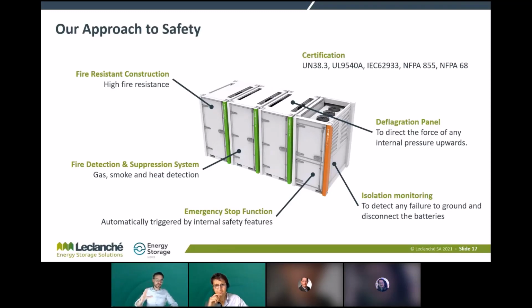The biggest improvement is clearly the concept itself with these portioned building blocks. That means we no longer have large battery room installations. Each battery block is a closed unit with a high fire resistance rating, so in the event of a fire there's an unlikely possibility of propagation from rack to rack, since the system is already enclosed.